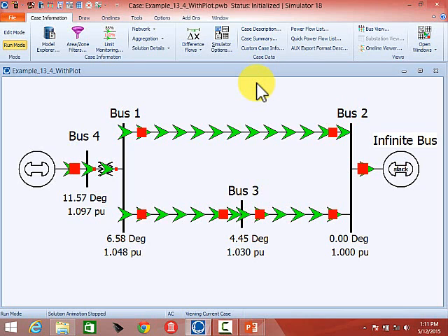This is actually a useful concept that we'll cover later on when we talk about play-in models, which are used for PMU validation studies, because play-in models allow you to have an infinite bus where it's assumed it's such a large generator, nothing that occurs out here affects that generator. But rather than keeping it constant like we will do in this example, with a play-in model, you can play in how the generator actually responded during a disturbance from recorded data, and its frequency and voltage will vary as it actually did. And we'll get to that later on.